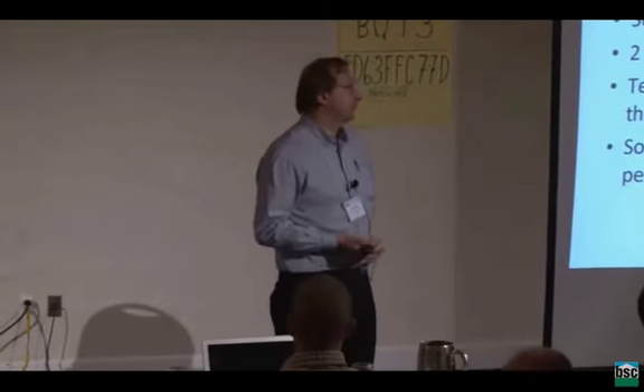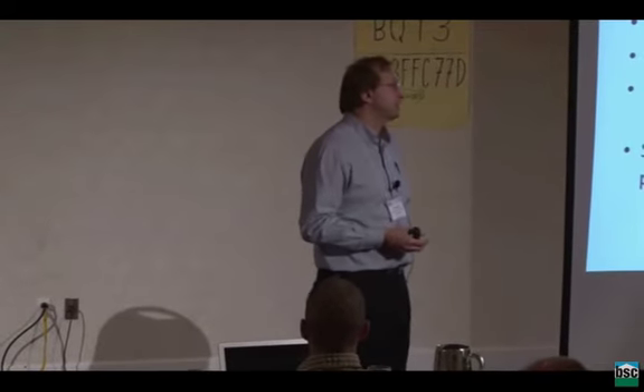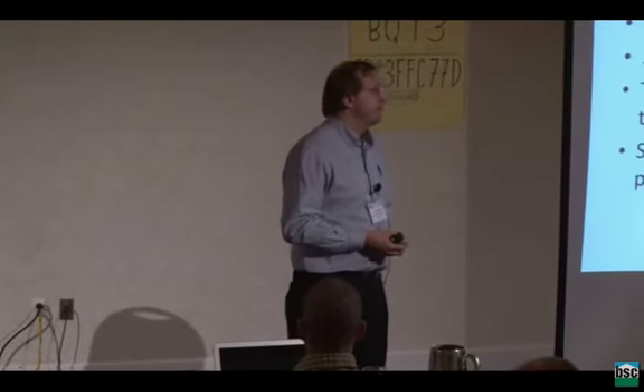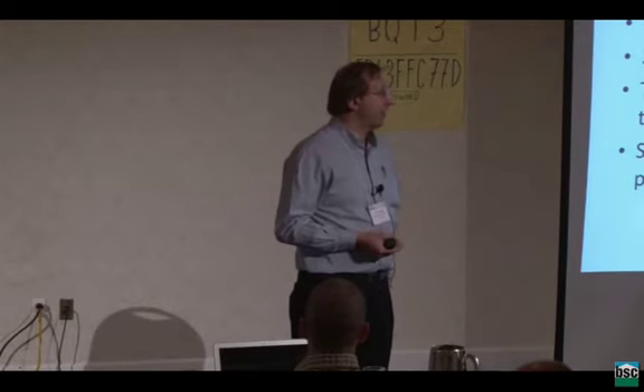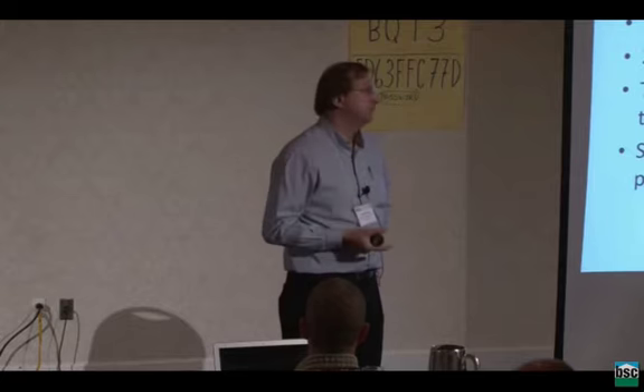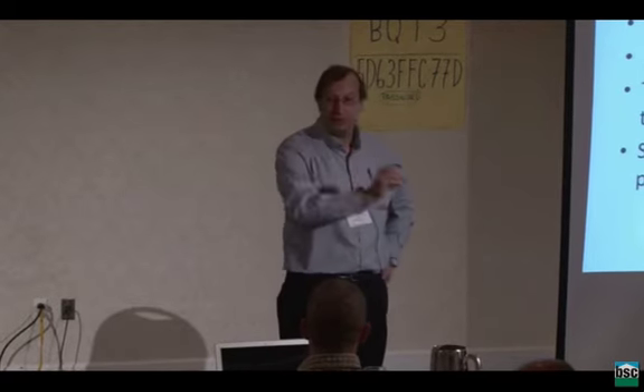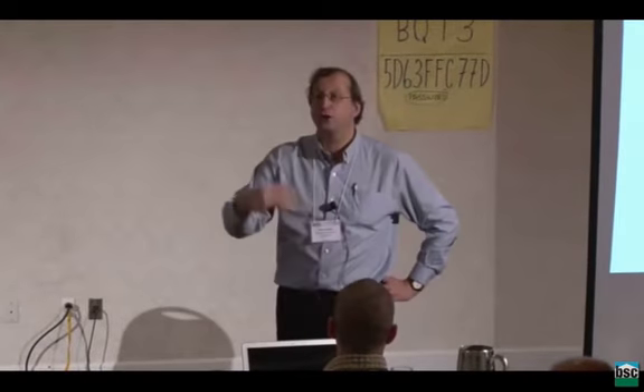I think it's just a completely reasonable question to ask: why is 5 degrees good enough and 5.5 not, and should it be 3? And for how long? How long can we deviate from set point? Because this is holding back the adoption by large-scale builders, because they don't want to get into trouble saying that, well, we had comfort complaints and we didn't meet the 5 degrees requirement. And some people probably want it more constant than others, right?